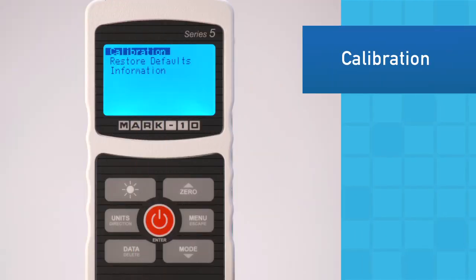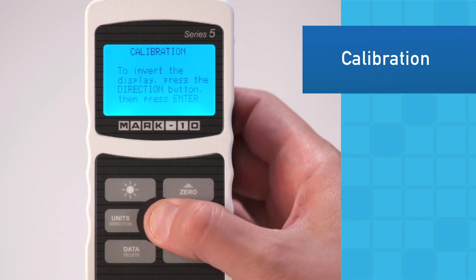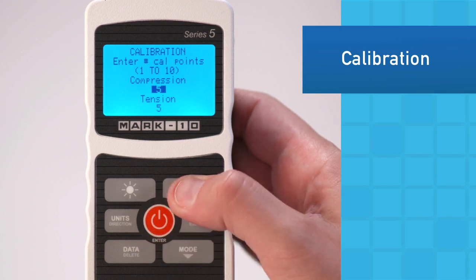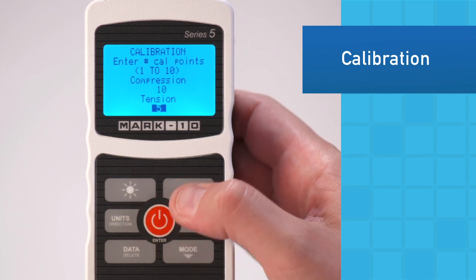Calibration is easily done utilizing deadweights or reference load cells. The user may select up to 10 data points in each measuring direction and may specify the exact weights of each data point in any supported unit of measurement.